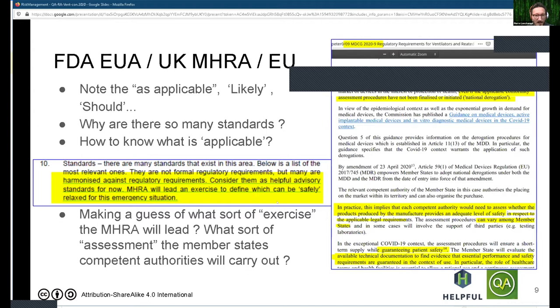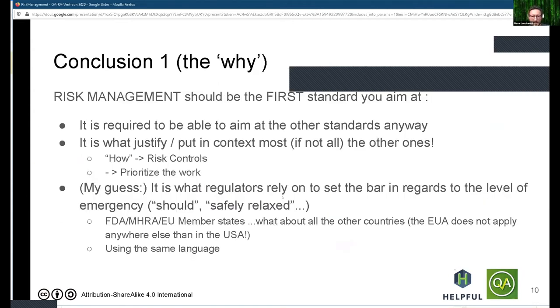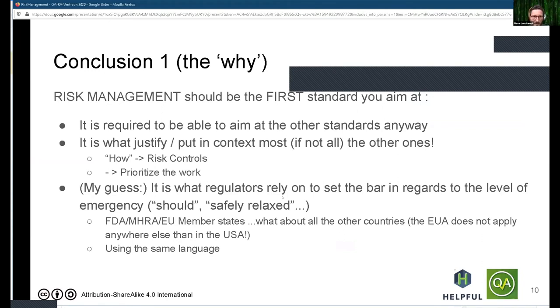For those reasons, I believe risk management should be the first standard you aim at before you even want to dig into 60601 or 62304. You should be looking at 14971, understanding the process of risk management, and start documenting and applying it within your teams.